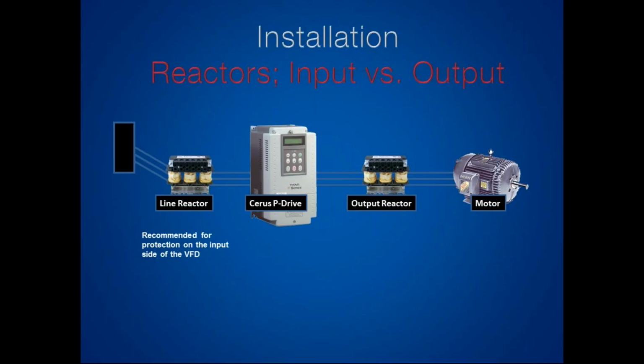Reason being is that the drive is usually going to be mounted pretty close to the motor, okay? So our rule of thumb is 100 feet. If your drive is going to be mounted over 100 feet from your motor, we're going to go ahead and include an output reactor, okay?